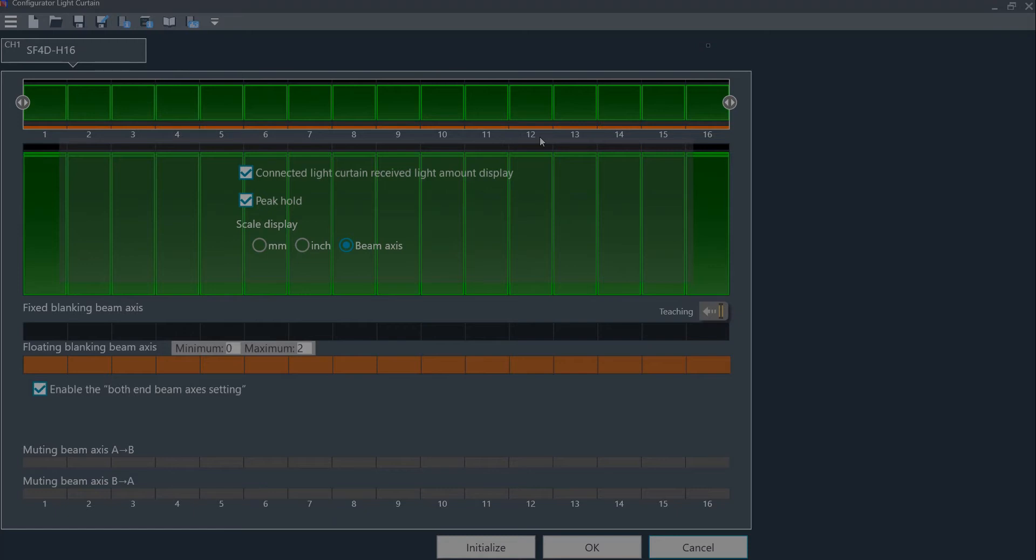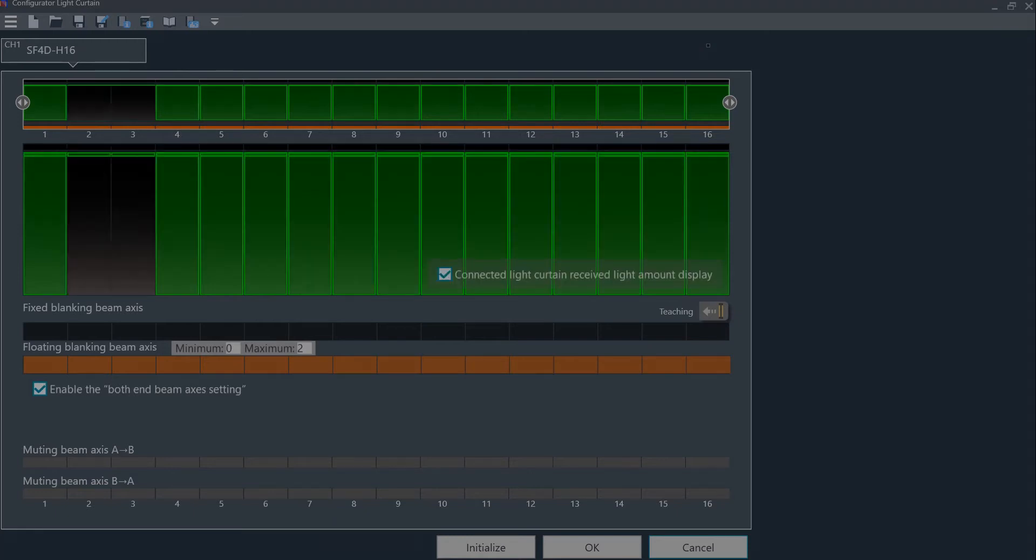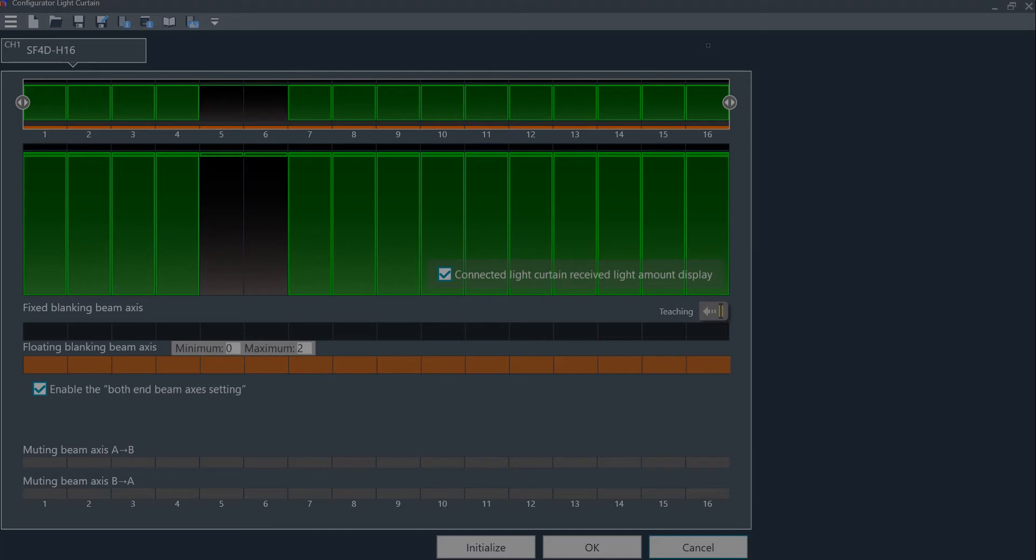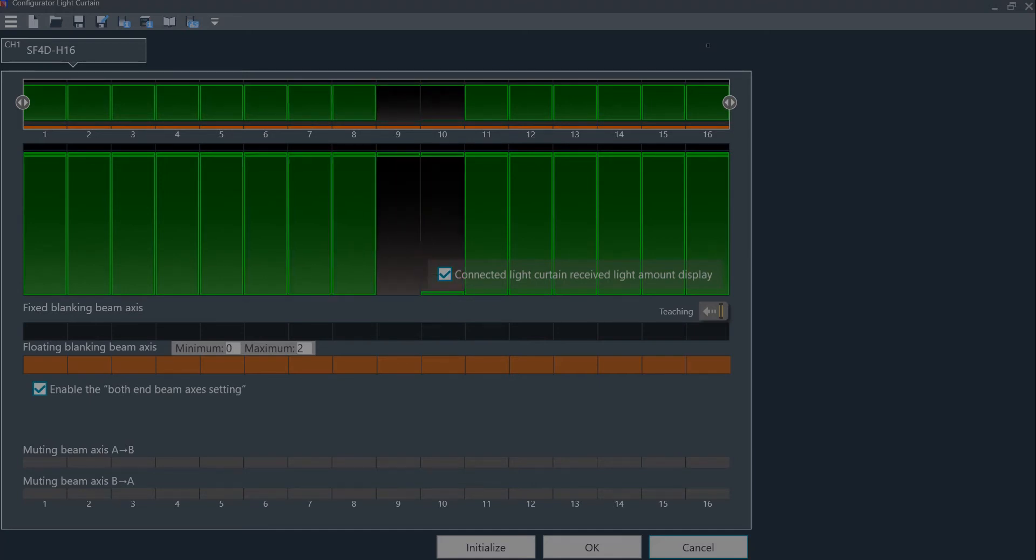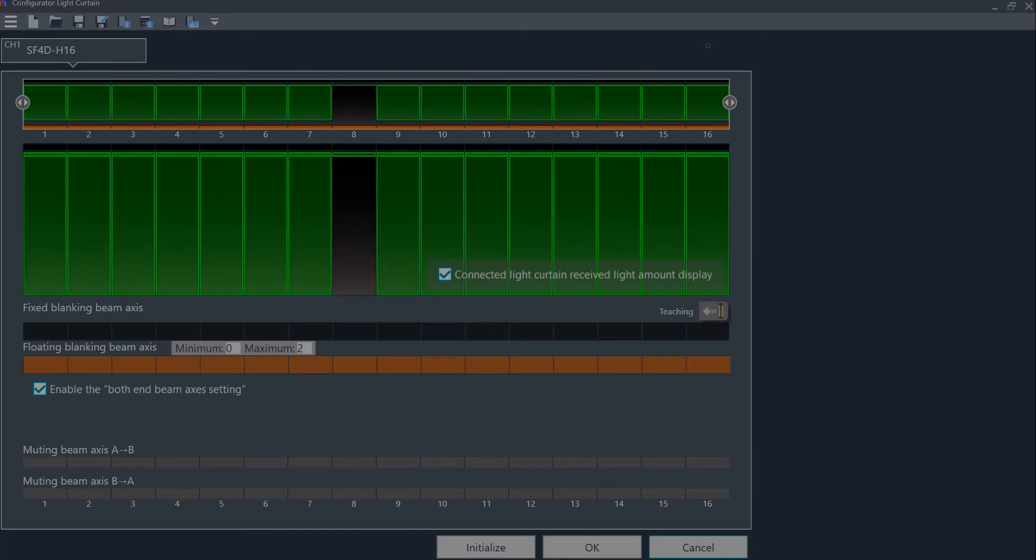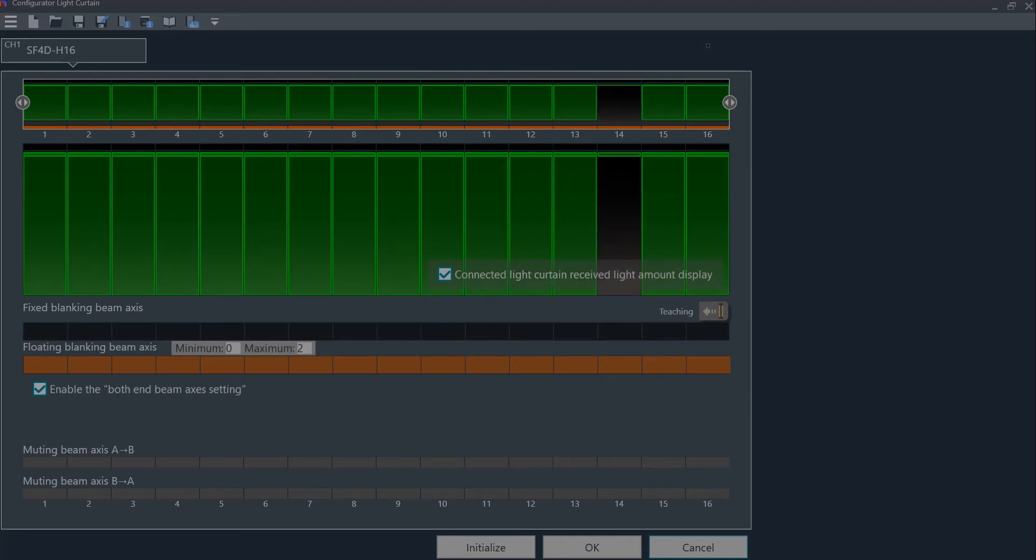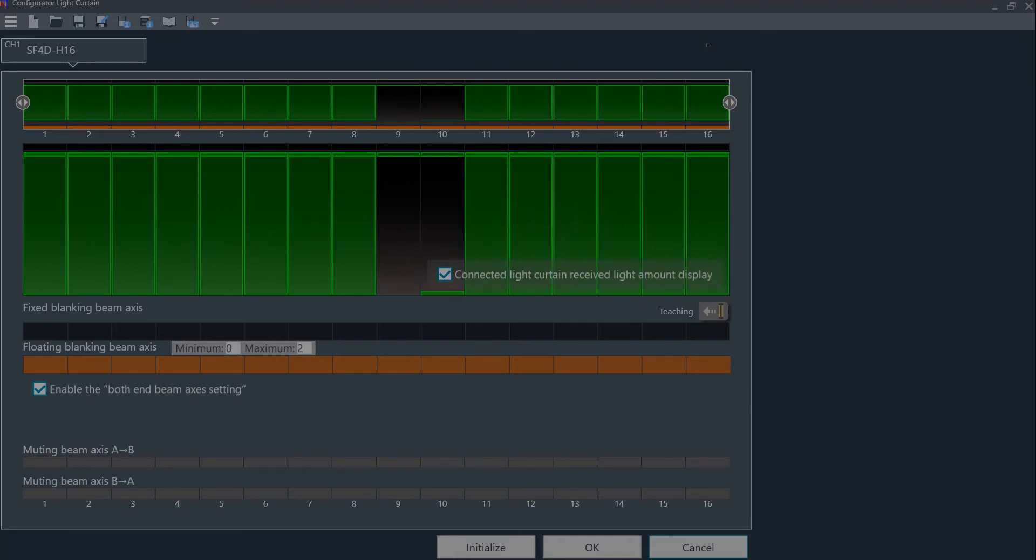Now I will put an object in the beam to simulate the coil. As you can see, the object is passing through the active area of the light curtain and blocking two of the light channels at a time, and the light curtain is in an unactivated state.